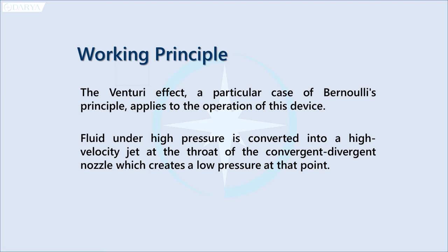Working principle is the venturi effect, a particular case of Bernoulli's principle applies to the operation of this device. Fluid under high pressure is converted into a high velocity jet at the throat of the convergent-divergent nozzle which creates a low pressure at that point.